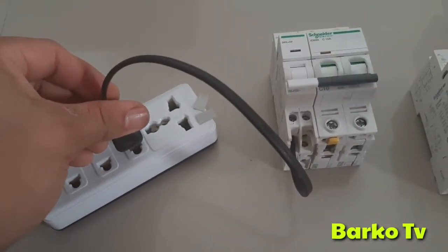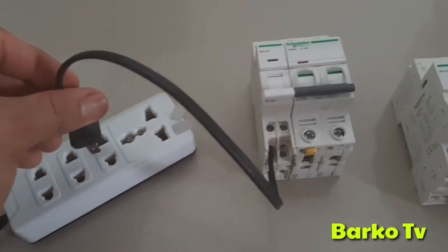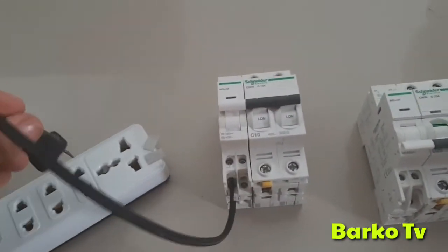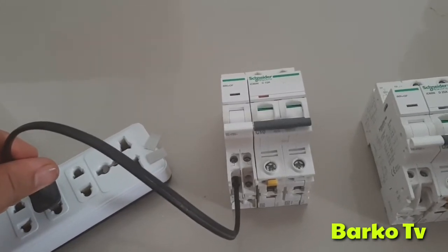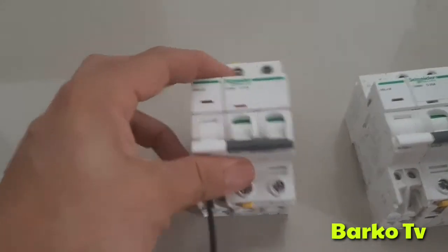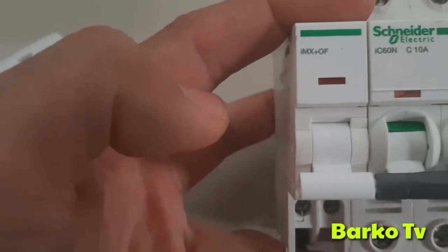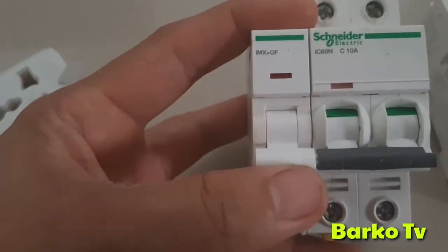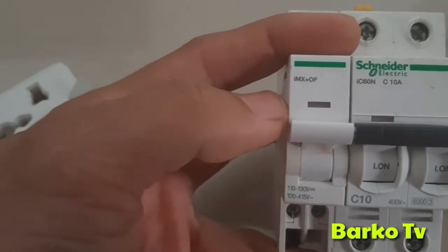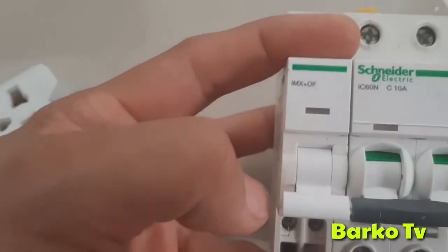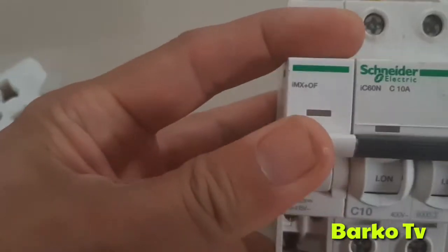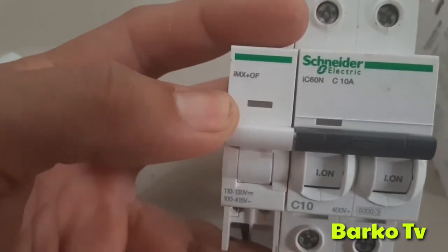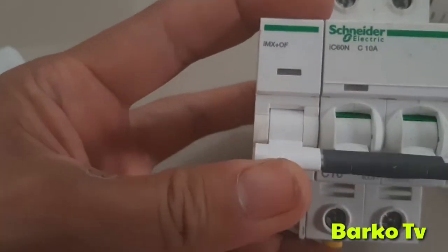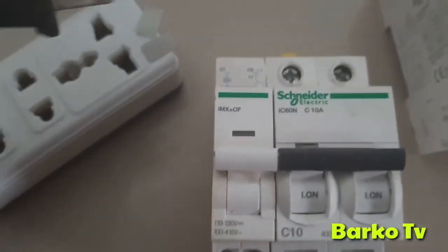I show you the single-phase MCB. If you put supply on it, it will trip. See, there is an indicator at the top. Means it is activated. If the color is unchanged, that is normal. Then it's not tripped yet. If you supply the coil, it will change the indicator color to trip. I mean, it's activated.